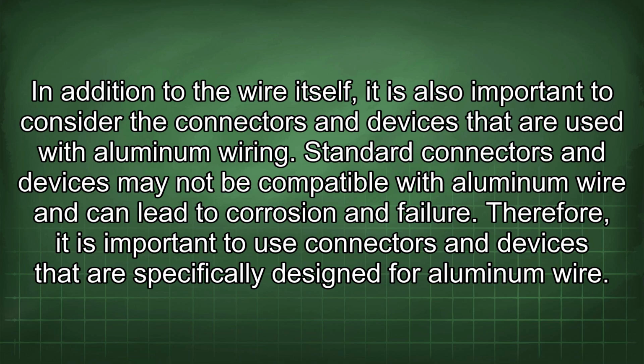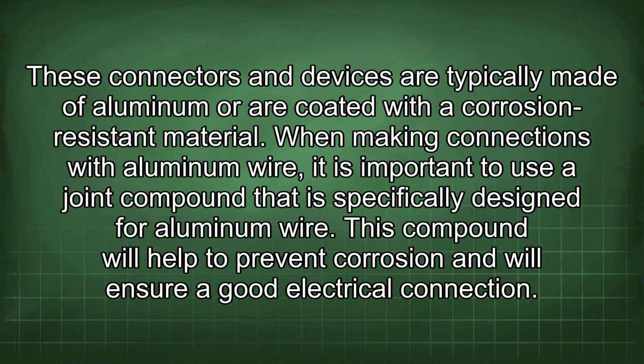Standard connectors and devices may not be compatible with aluminum wire and can lead to corrosion and failure. Therefore, it is important to use connectors and devices that are specifically designed for aluminum wire. These connectors and devices are typically made of aluminum or are coated with a corrosion-resistant material. When making connections with aluminum wire, it is important to use a joint compound that is specifically designed for aluminum wire. This compound will help to prevent corrosion and will ensure good electrical connection.